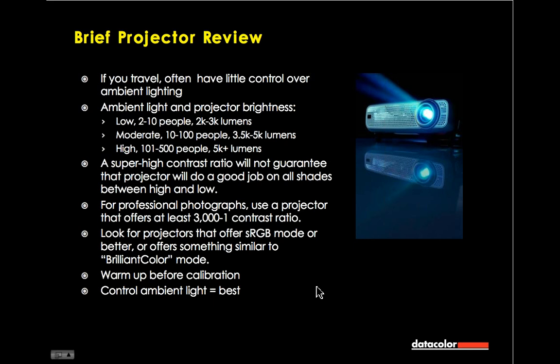When you're going to use one of these machines, do warm it up before you use it or before you calibrate it. They do change pretty dramatically in the first couple of minutes. It's really not a good idea to walk in, plug the thing in, and start right away. That's definitely not good. If you can give it 10 or 15 minutes of running with a slide on the screen before you really get going, that would be great. You want to calibrate it obviously before you start, and it's a 10-minute cycle, so it's not that much of a demand on your time, and if you can arrive a little bit ahead of time, no big deal. And again, I come back again and again to control that ambient light, because that's your friend.